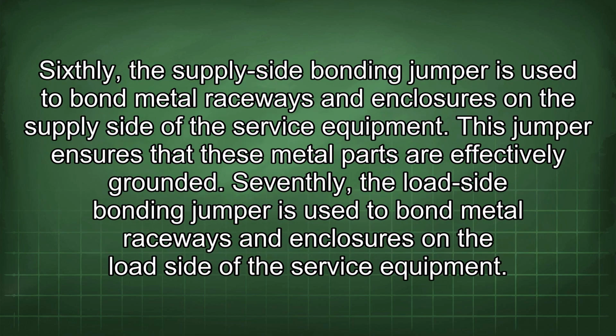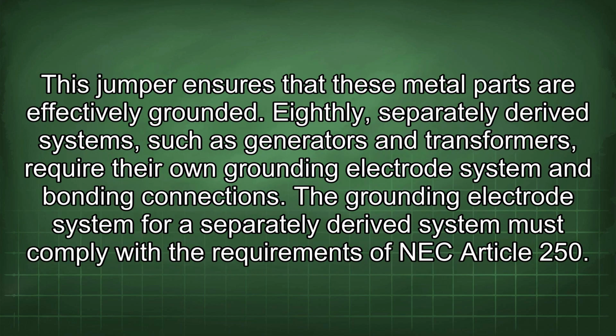Sixthly, the supply side bonding jumper is used to bond metal raceways and enclosures on the supply side of the service equipment. This jumper ensures that these metal parts are effectively grounded. Seventhly, the load side bonding jumper is used to bond metal raceways and enclosures on the load side of the service equipment. This jumper ensures that these metal parts are effectively grounded.